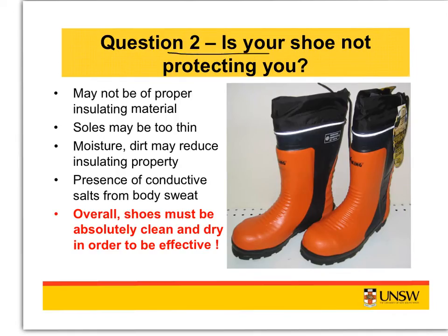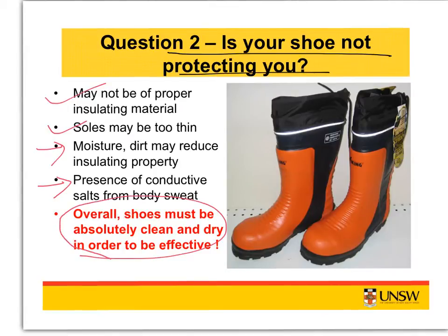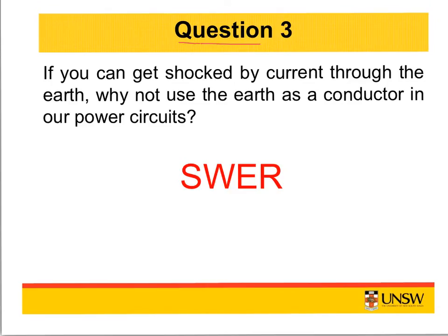The second question now is, is your shoe not protecting you? Okay, so normal footwear is not enough to guarantee protection against electric shock from a power system because the shoe may not be of proper insulating material, the soles may be too thin, and moisture and dirt may reduce the insulating property. The presence of conductive salts from the body sweat also provides a path for conduction. Overall, the shoes must be absolutely clean and dry in order to be effective. So special shoes made of rubber are good enough, but they have to be absolutely clean and dry to provide proper safety.